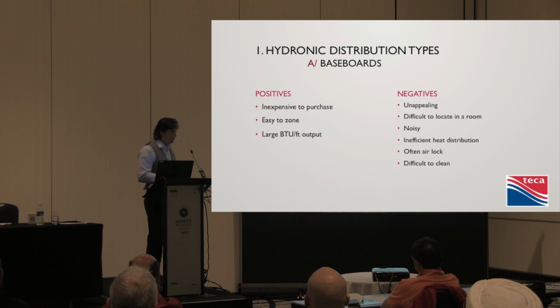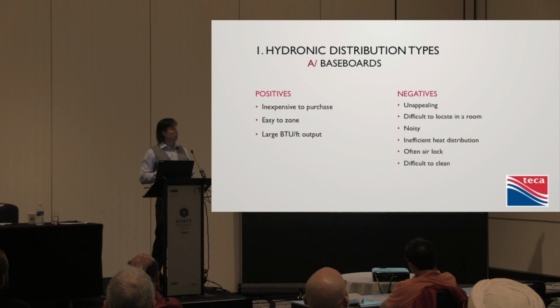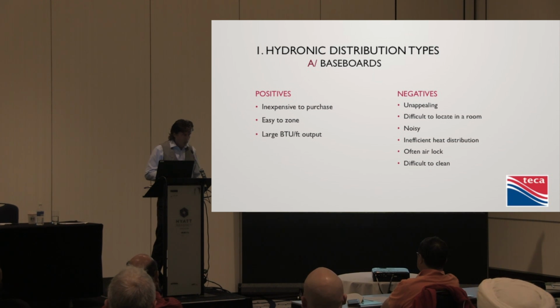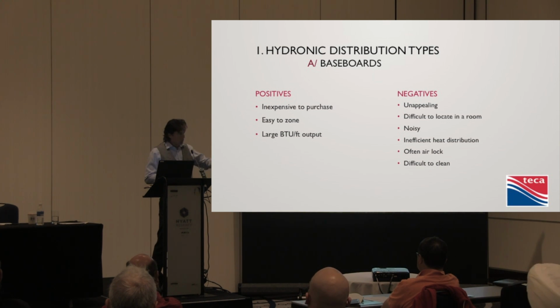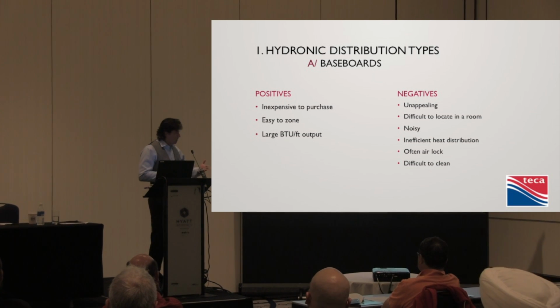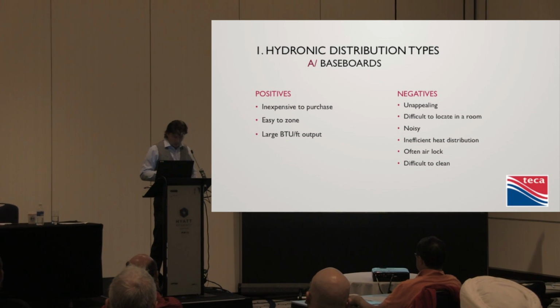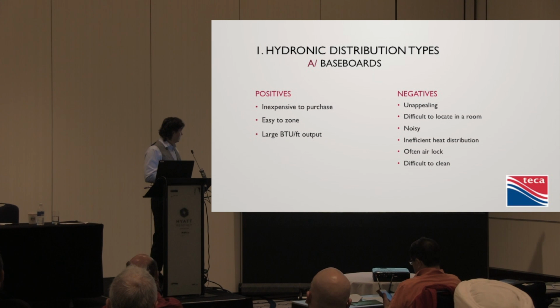Inefficient heating distribution. Well, okay, in this room, if we were to put a baseboard right over there, what's going to happen is that cold air is going to come up and it's going to rise up here, and then it's going to just swirl around here and kind of hang around there because we're heating air convectively. So not the best way to heat a room. It's mostly used in perimeter heating below windows, so it'll form that warm curtain. But as far as keeping the room comfortable, it's not so good.